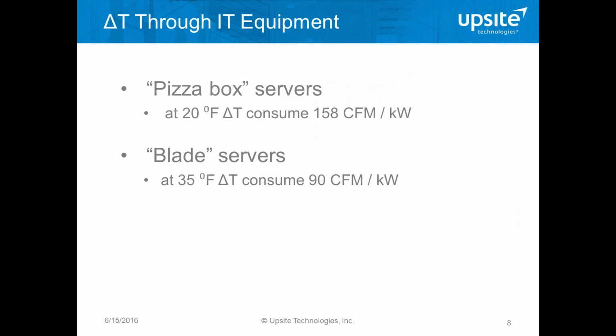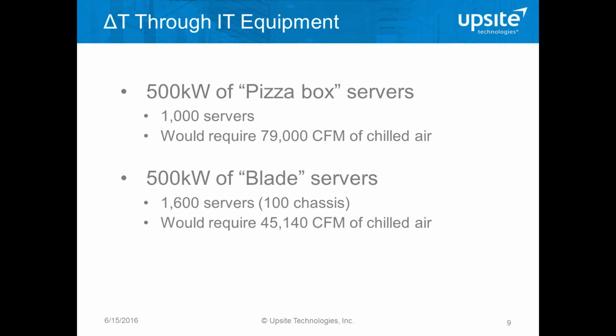So here we look at a typical pizza box server versus a typical blade server system, and the airflow requirements are required to serve the delta T's of those servers. Next. And so at a 0.5 megawatt example of the data center, we can see that our flat servers are consuming or requiring almost 75% more air than our blade systems. And that has a direct impact on both the operational cost and acquisition and capital costs per data center. Look at the next slide.